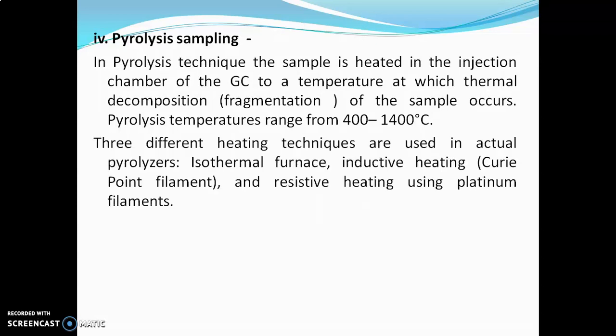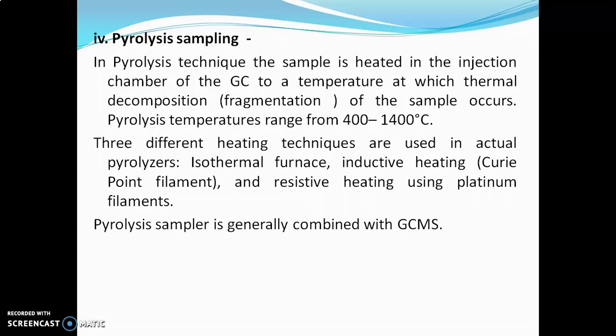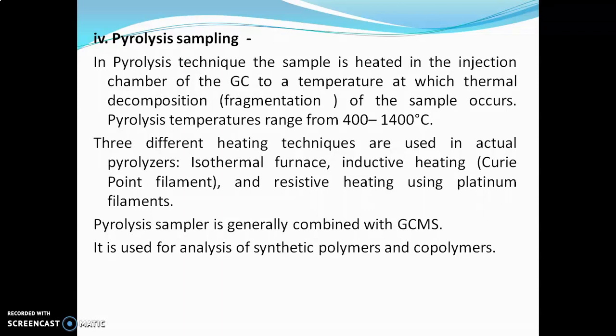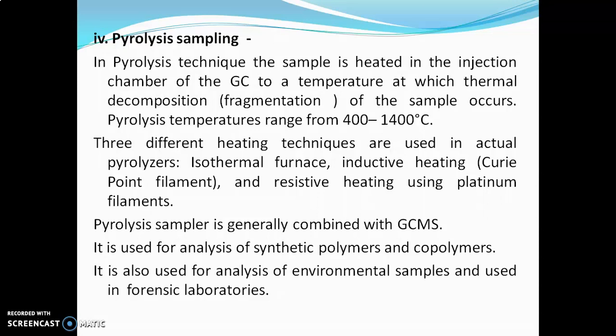In pyrolysis sampling, the sample is heated in the injection chamber of GC to a temperature at which thermal decomposition — that is, fragmentation — of the sample occurs. Pyrolysis temperature ranges from 400 to 1400 degrees Celsius, and higher temperature pyrolyzers are also available. Three types of heating techniques are used: isothermal furnace, inductive heating (curie point filament), and resistive heating using platinum filaments. Pyrolysis samplers are generally combined with GC-MS (gas chromatography-mass spectroscopy) and are used for analysis of synthetic polymers, copolymers, environmental samples, and in forensic laboratories.